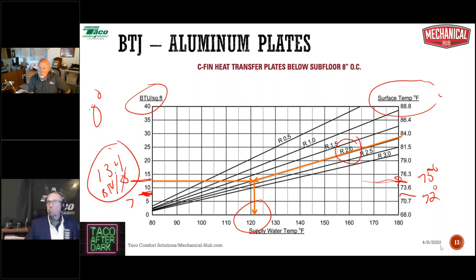Someone asks about standalone thermostats. Okay, I see that popped in there. Floor sensor, a good idea. Yeah, floor sensors are great as long as it adds something to the job, as far as the installation of the floor sensor as well as the dollars that are involved. But typically, we would recommend floor sensors when we had a potentially problematic floor covering, like an exotic hardwood where you can never exceed 82 degrees, and we could set some high limit parameters for that.